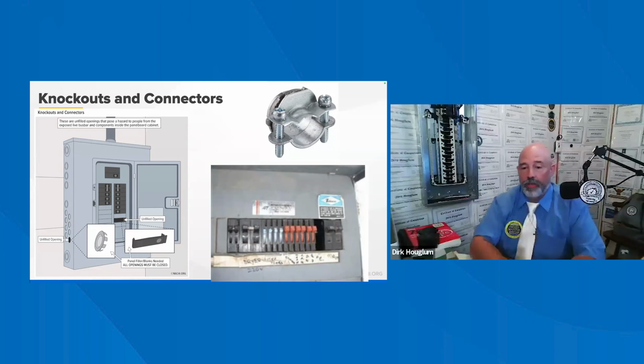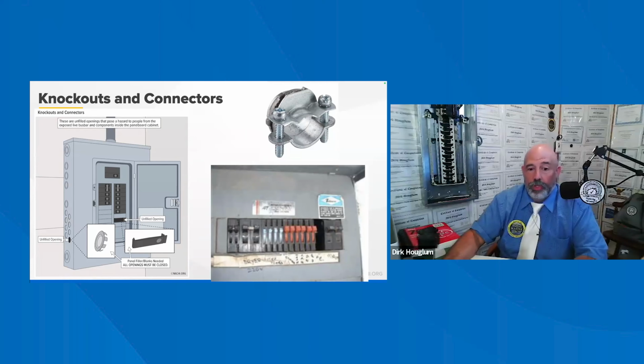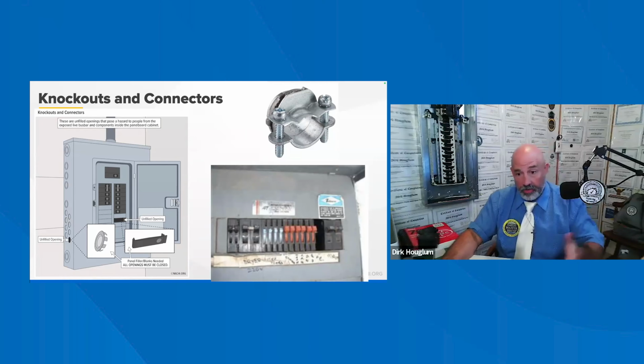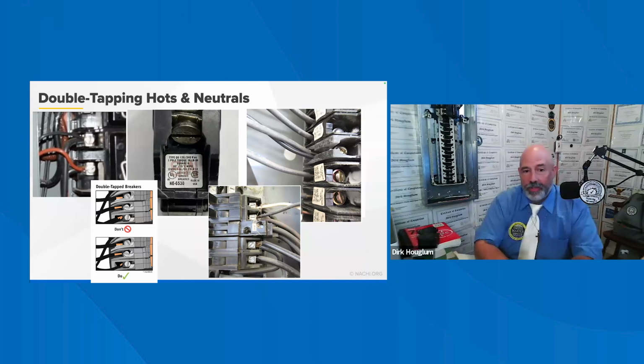And you can tell by the earlier slide that I have about things that can happen to children and other adults if something like that happens. We want to make sure that we're looking at the double taps. Even double tap neutrals and grounds need to be called out, because one might expand a little bit or shrink a little bit, and we are looking at double taps or double lugging as a potential to have an arc.